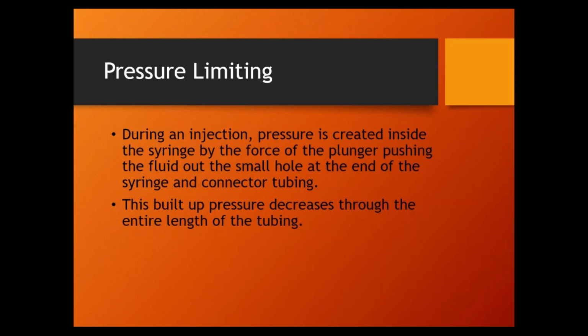So, what happens is during the injection, yes, inside the syringe, let's say, for instance, we do a peak out. Let's say we get 1,200 PSI in the syringe here. But when we go from this 1.5 inch wide bore here down to this 1 millimeter wide bore here, we literally go from 1,000 PSI to 2 PSI. And the closer we get to the end of the catheter, where the fluid's actually coming out inside the patient, we get closer and closer and closer to 0 PSI.